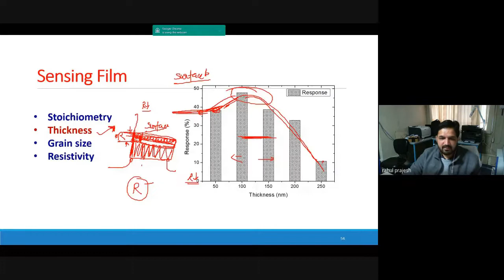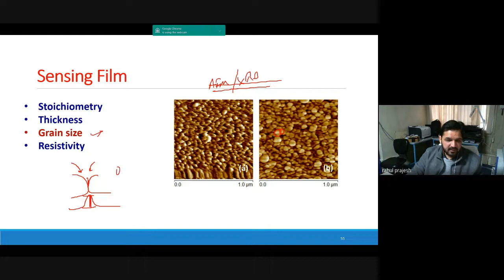These grain sizes are important, as I told you, in the working of the device. You have these grains, and at the grain boundaries you get the adsorption of the gases, and because of that there is a barrier height. This barrier height will either increase or decrease depending on the nature of the gas, whether it's an oxidizing gas or a reducing gas. Depending on that, it will increase or decrease.